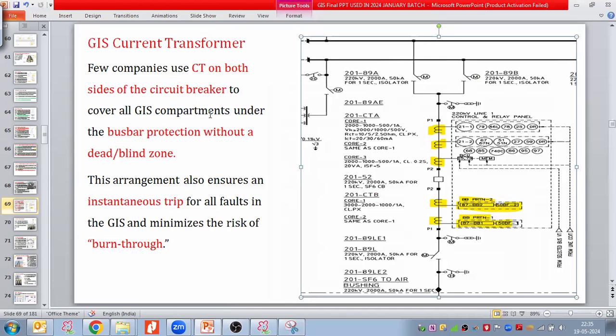Now coming to the CT. A few companies use CTs on both sides of the breaker, CT here and CT here. This covers all GIS compartments, modules or equipment under the bus bar protection without any blind zone or dead zone. This arrangement also ensures an instantaneous trip of the breaker for all faults in the GIS and minimizes the risk of GIS gas burn through.